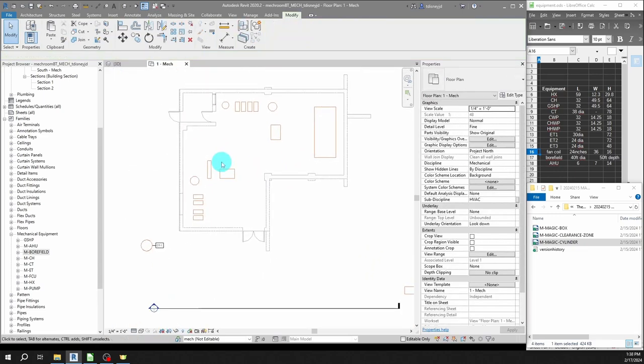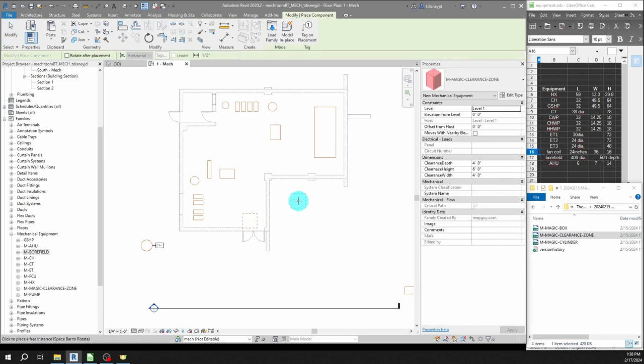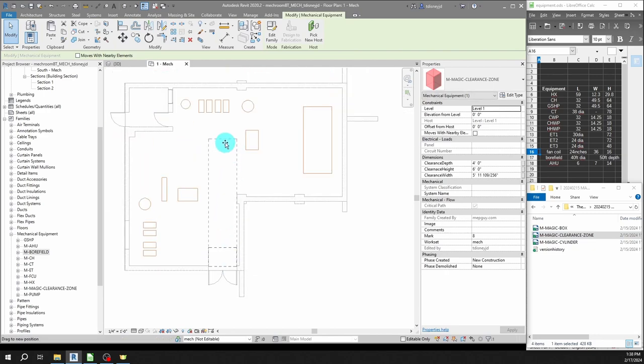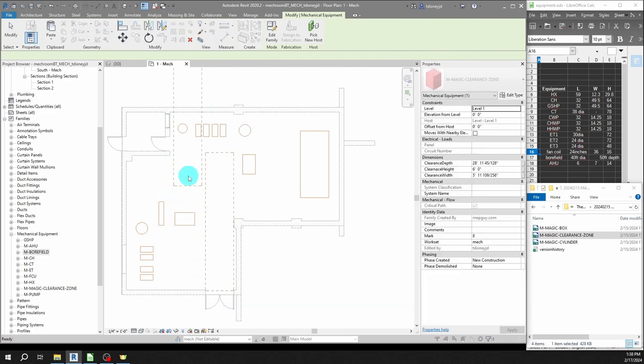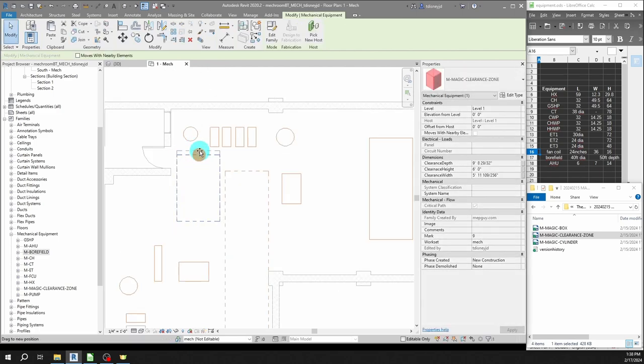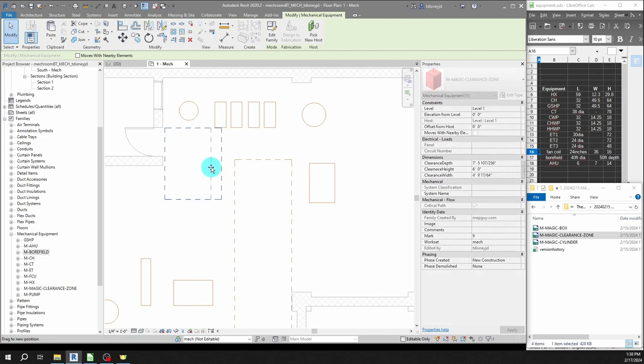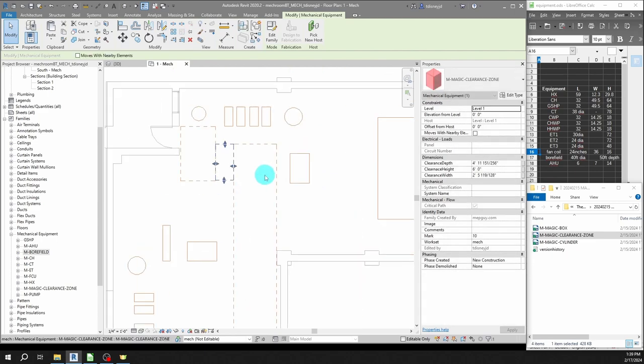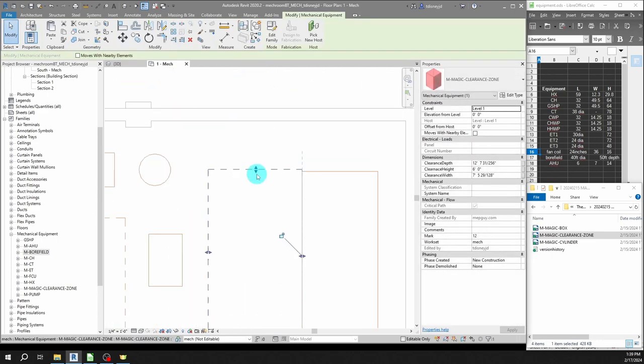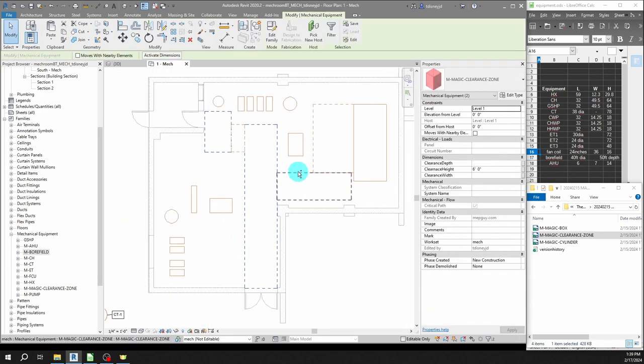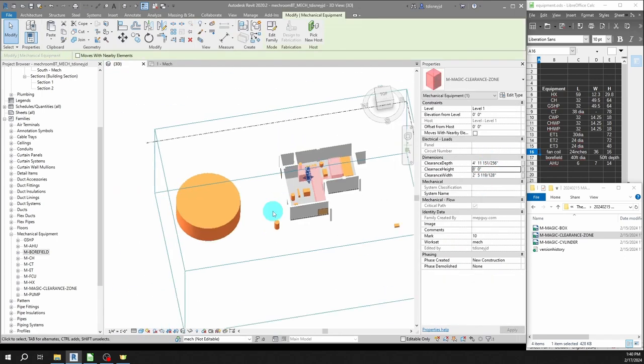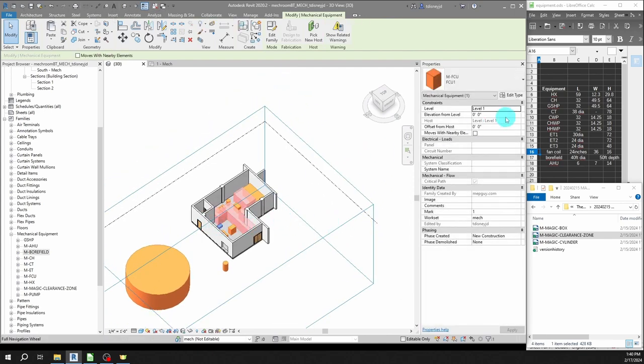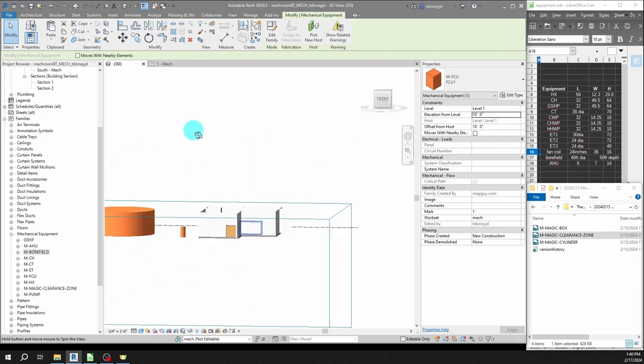That looks about okay. While I'm in here now, I think I'm going to put in some initial clearance zones. This is just a family that I use to indicate access to make sure that I don't make that oh so common engineer's error of designing a screw where you can't actually fit a screwdriver in. Don't be that guy, don't be that engineer, don't do it. Take a quick look in 3D. I've missed my fan coil unit, it should go about 10 feet off the deck, something like that, up in the ceiling.